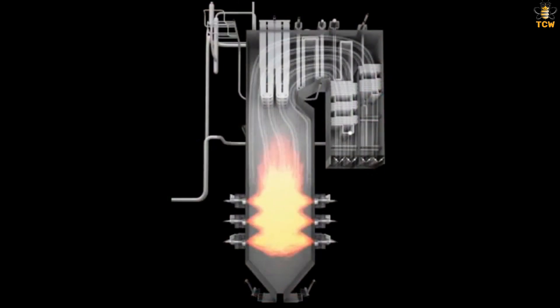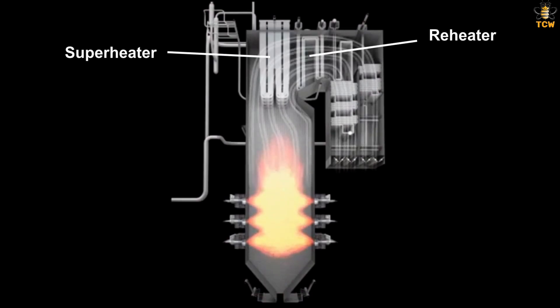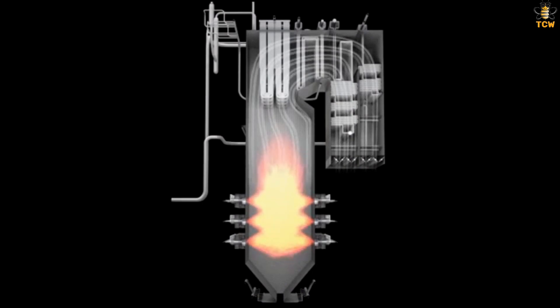The heating units in the boiler are units of pipes that contain feed water, consisting of a superheater, reheater, and economizer. The particulate-free flue gas flows first to the superheater, then to the reheater, and then to the economizer. The heat present in the flue gas is absorbed by the heating units so that the temperature becomes lower and lower. Meanwhile, the feed water in the heating unit pipes increases in temperature and becomes steam, which is then flowed to the turbine. The flue gas is then released through the chimney.